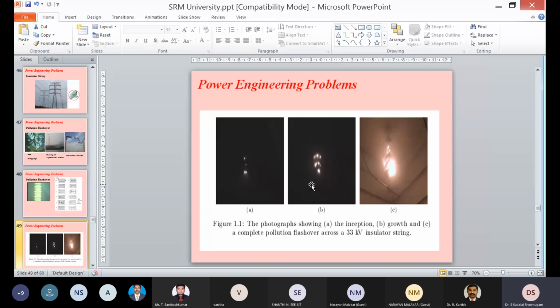This is how it actually happened in the field also. This pollution phenomenon won't happen in a newly erected line; it will take time. But the problem is, once the pollution flashover happens, it continues unless and until the pollution-causing environment is cleared. For example, I will give you a scenario. One of the critical sources of pollution flashover is bird droppings. We might have seen a lot of birds sitting on the transmission line and insulators, and they will drop on the insulator also. The problem is the bird droppings are highly acidic in nature.